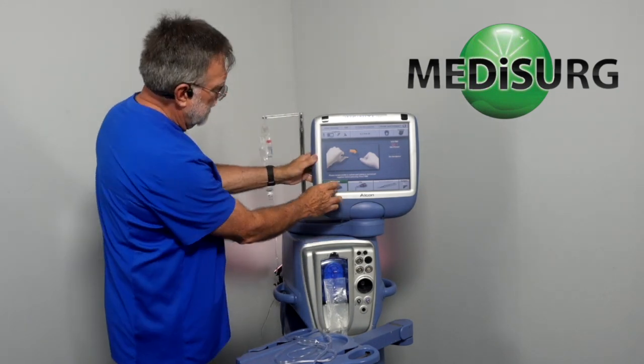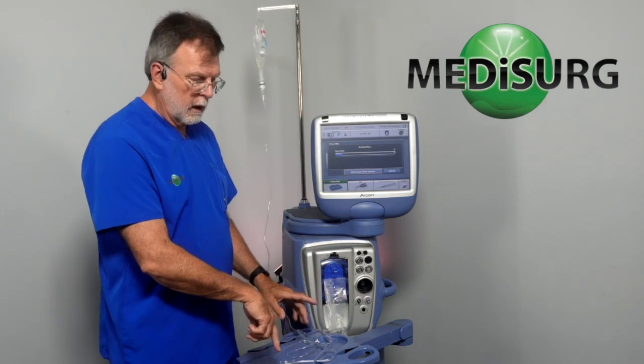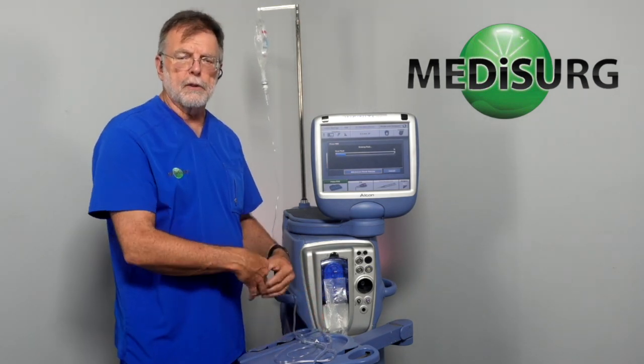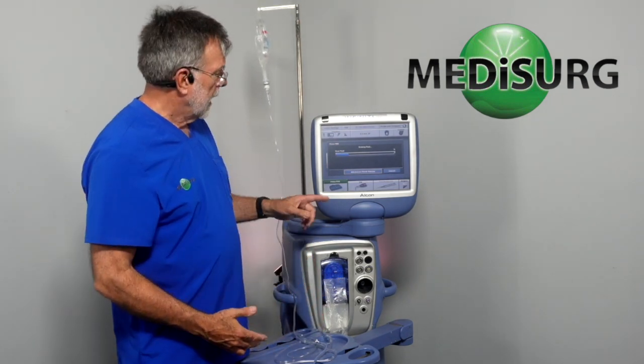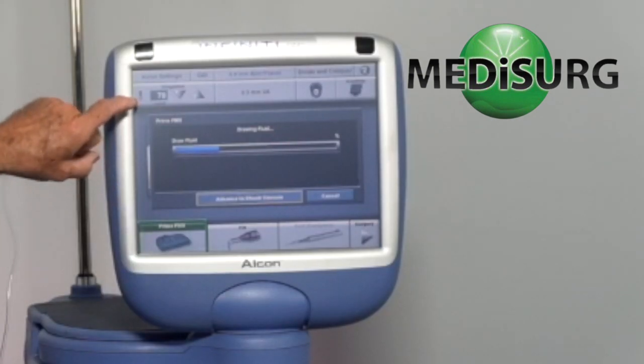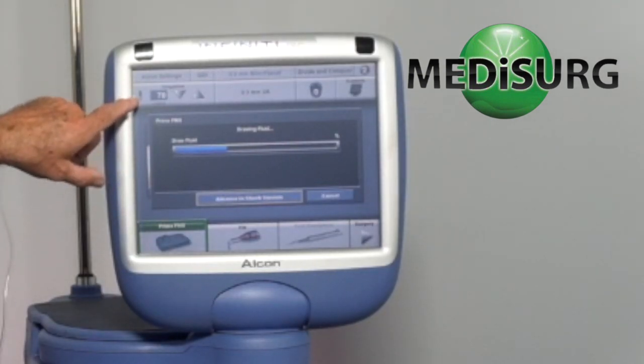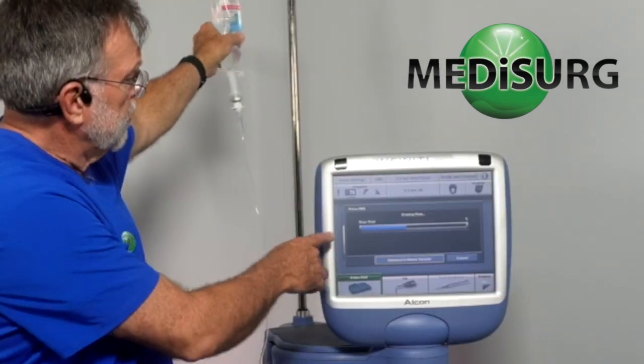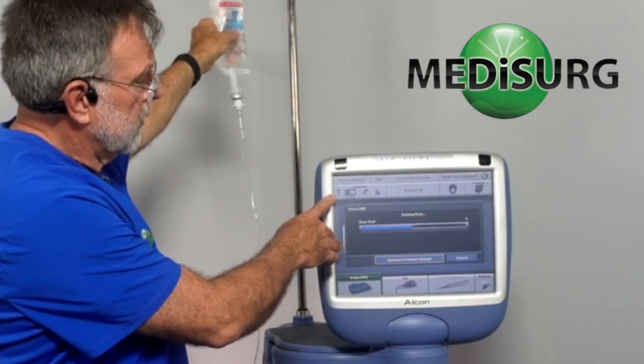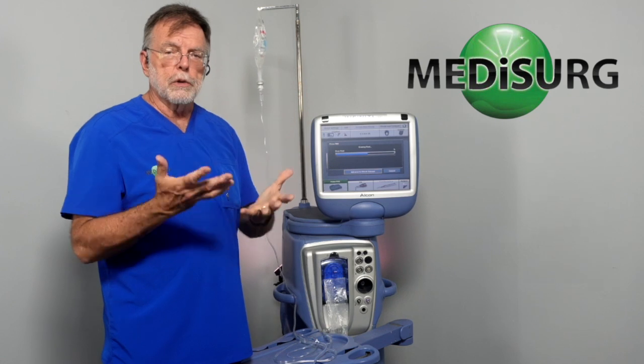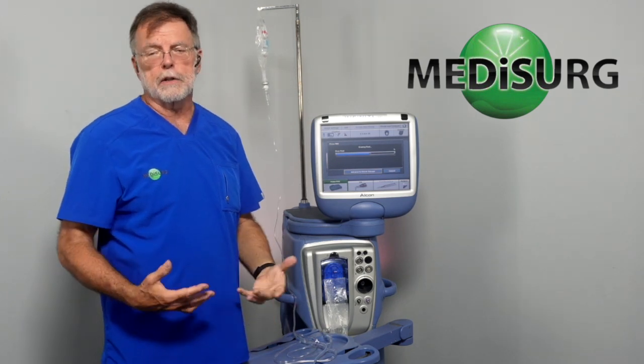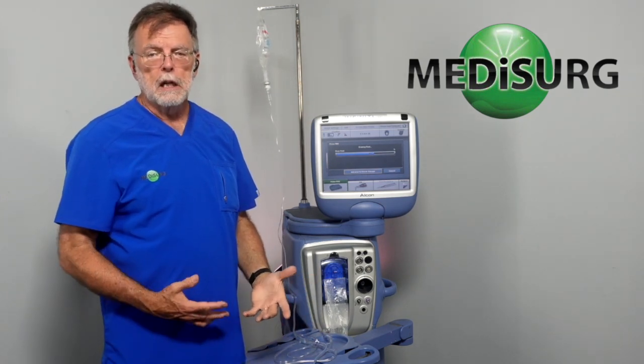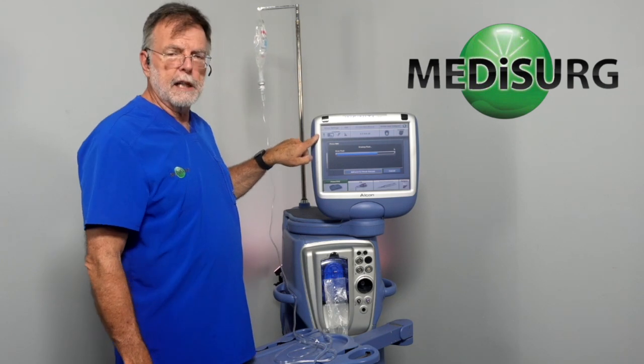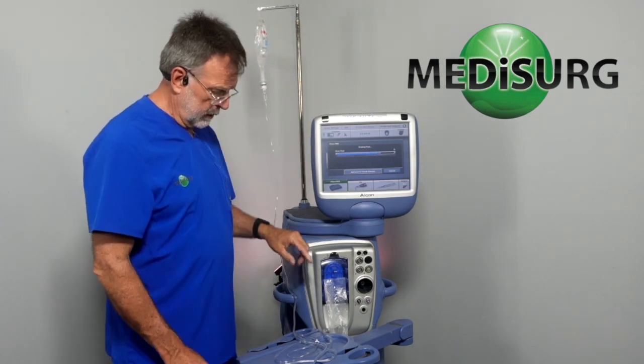We'll touch prime. Now during this priming sequence, what it's doing is pulling all the air out of the system. It's filling the lines with fluid. And you can see in the upper left-hand corner here, this is the irrigation pressure sensor readout. So if I were to squeeze this bottle, we could get that sensor to move. If the bottle or the bag was too low, it's going to sense not enough pressure. So that's a helpful indication as to what's going on with the irrigation pressure.